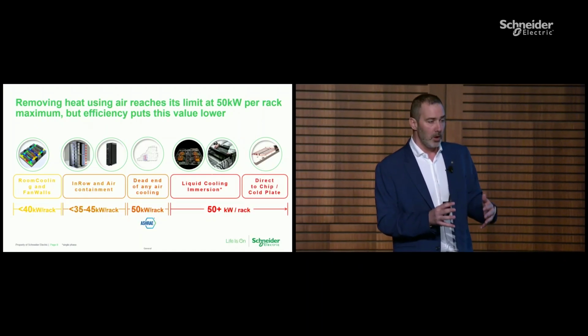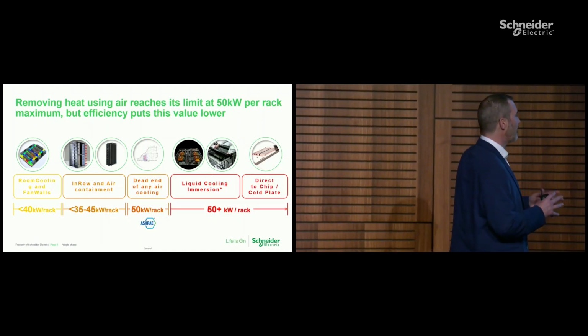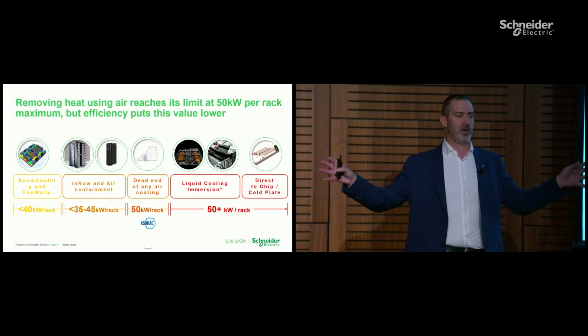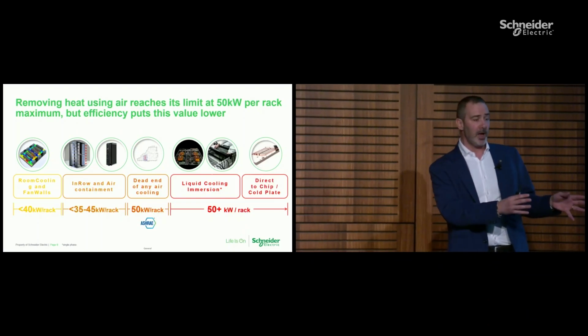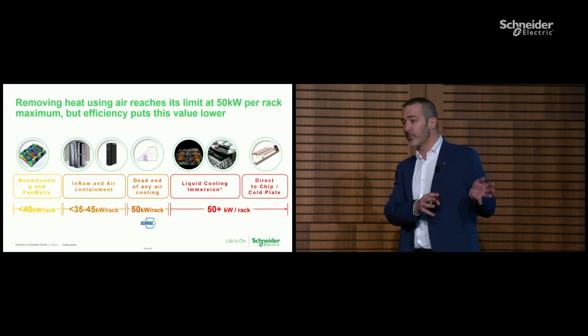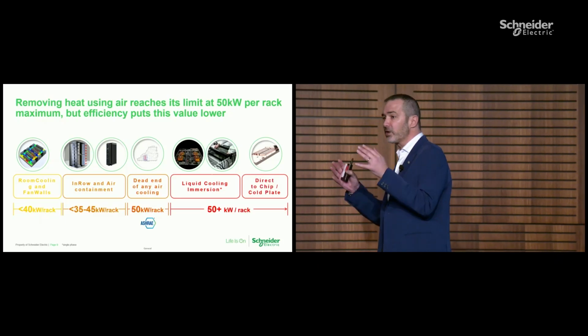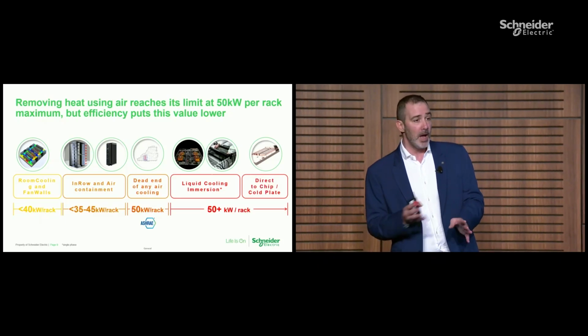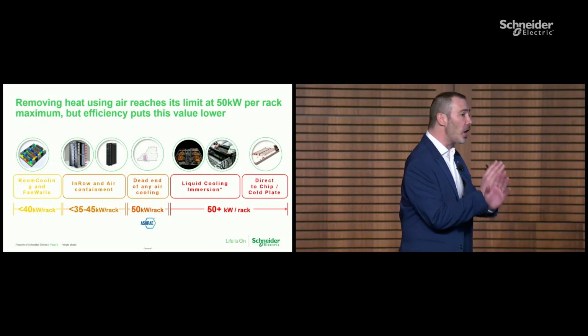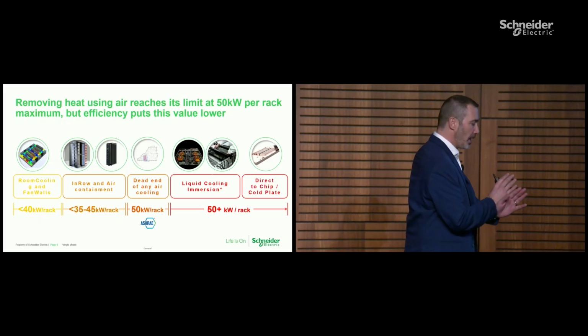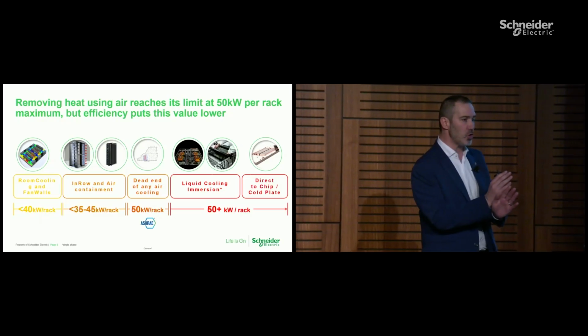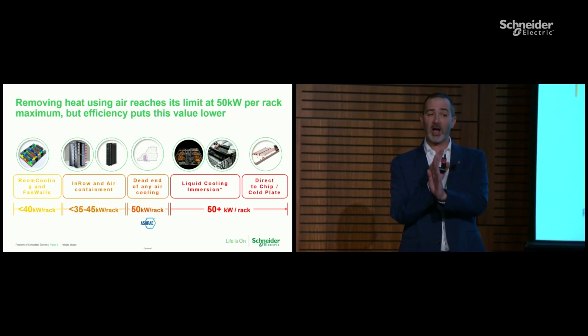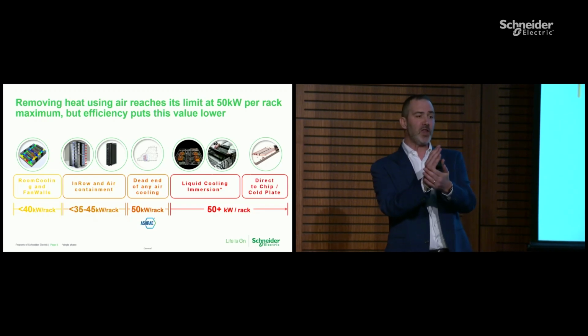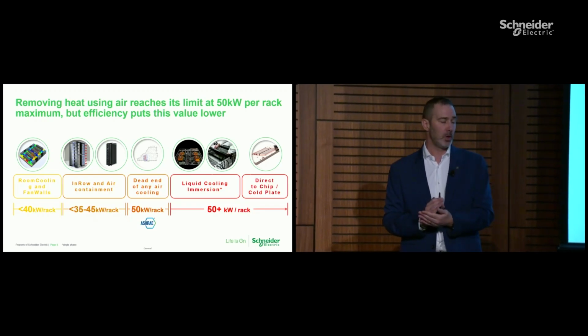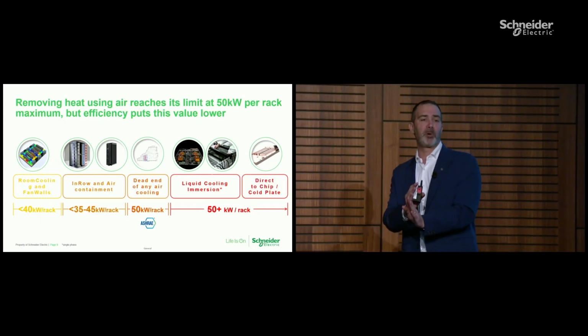But really, looking at this evolution, there are two big areas where air and liquid coexist, and where liquid cooling is mandatory, period. In between, and that's not a technological choice but primarily a choice coming from the ASHRAE guideline, there's the 50 kilowatt per rack threshold. Why is there a 50 kilowatt per rack threshold?